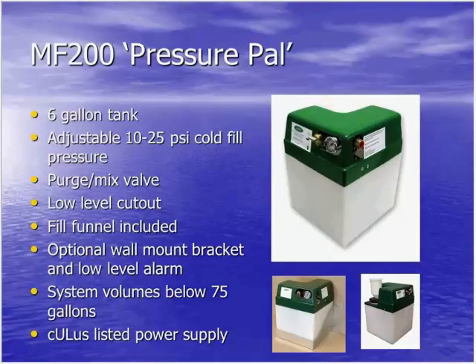It has a purge and mix valve, which allows the pump to self prime on startup. But it's also a nice feature in that if you're going to do service or modification to a system that's pressurized, you can simply unplug the unit, open up that valve, and the contents of the expansion tank are going to come out and back into the feeder tank. So you don't have to physically drain fluid from somewhere else in the system. So you go ahead, do your service or modification, close it back up, dump whatever fluid you may have collected during your service back into the tank. And once you plug it back in, it's just going to simply feed back into the system to pressurize it back up.